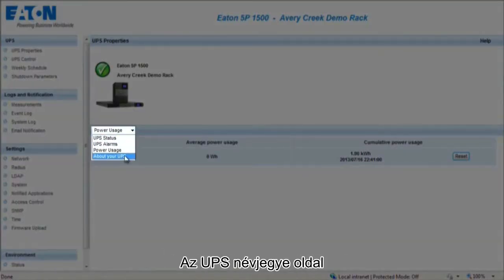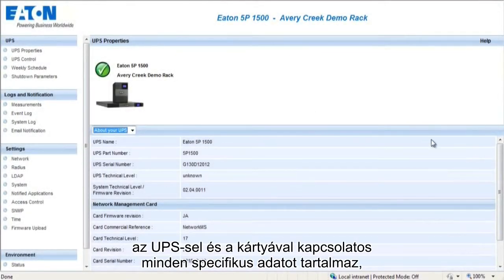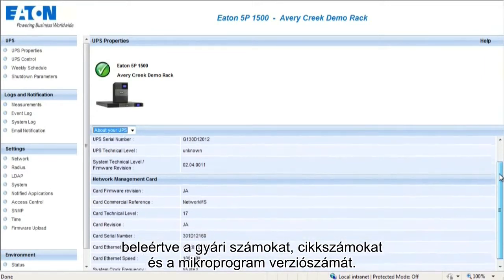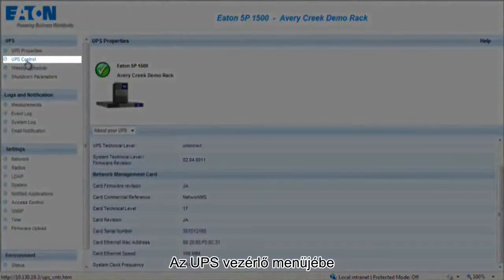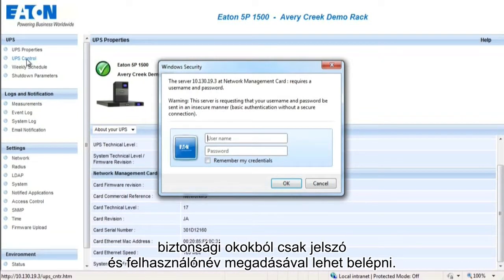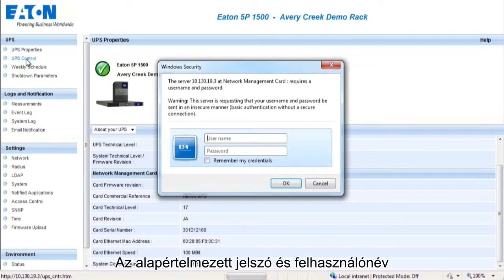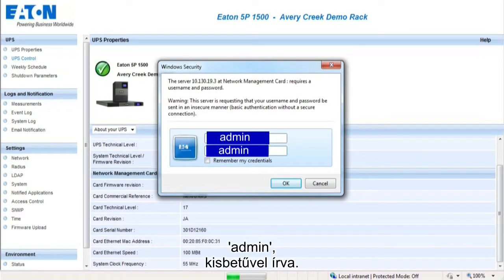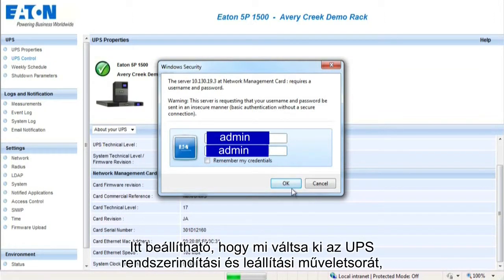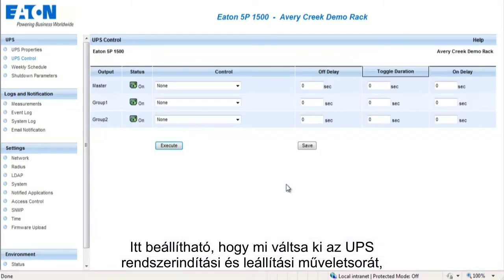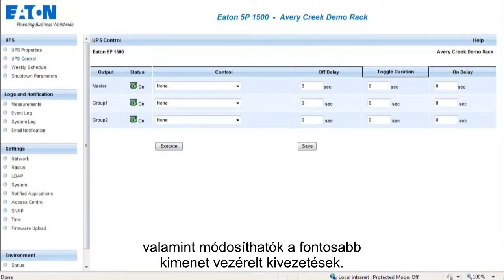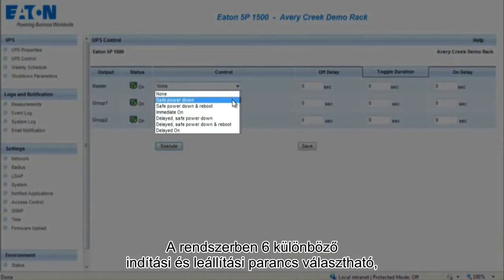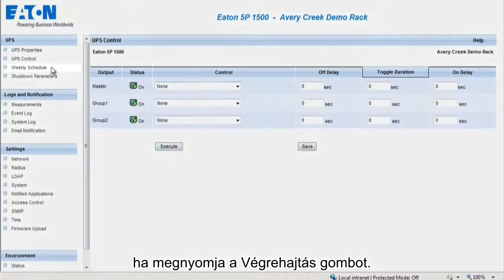The About Your UPS page provides all of the specific details on the UPS and card, such as serial numbers, part numbers, and firmware version. The UPS Control section requires a password and username for security purposes. The default password and username will be admin in lowercase letters. This page enables triggering of startup and shutdown sequencing for the UPS and main output controlled outlets. The system provides 6 different startup and shutdown commands which can only be enabled by selecting execute.